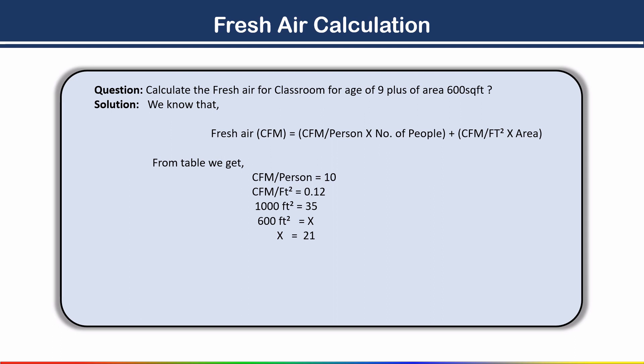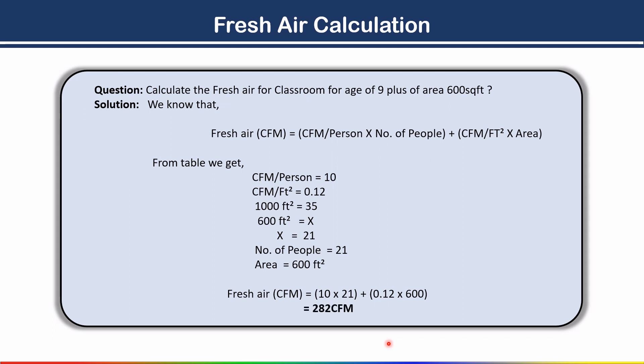The number of people in the classroom age 9 plus is 21. The area is 600 square feet. Now using the formula: Fresh Air CFM = (CFM per person × number of people) + (CFM per square feet × area) = (10 × 21) + (0.12 × 600) = 282 CFM. This is our fresh air CFM. This is how you calculate the fresh air CFM for your space. This is all about fresh air calculation.